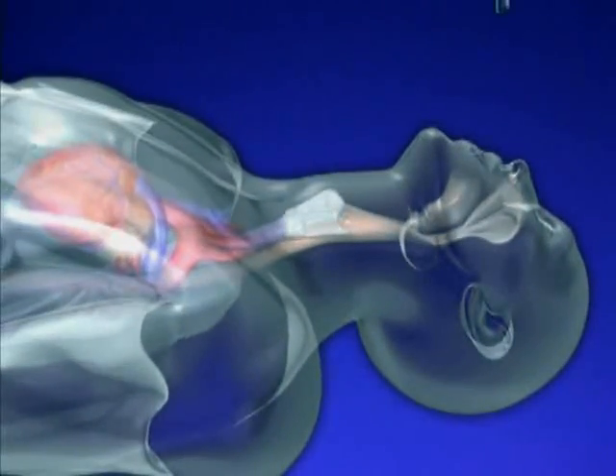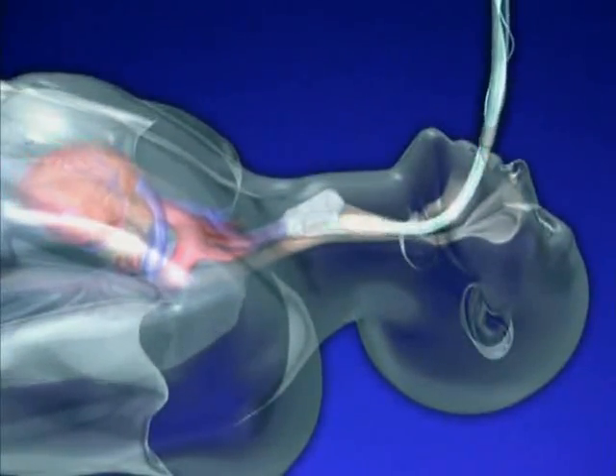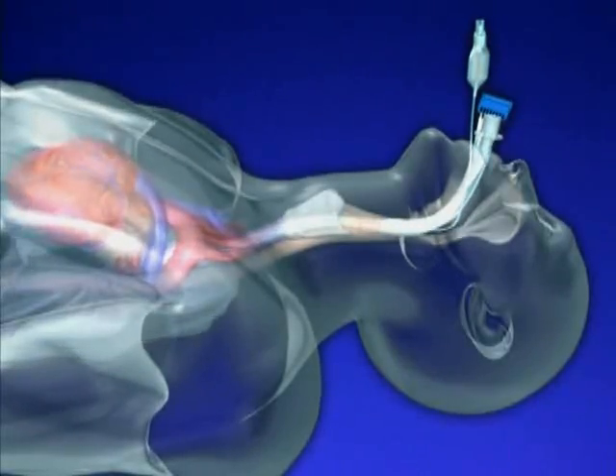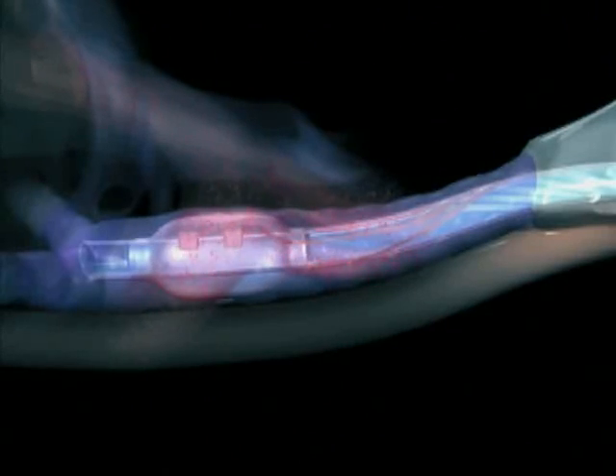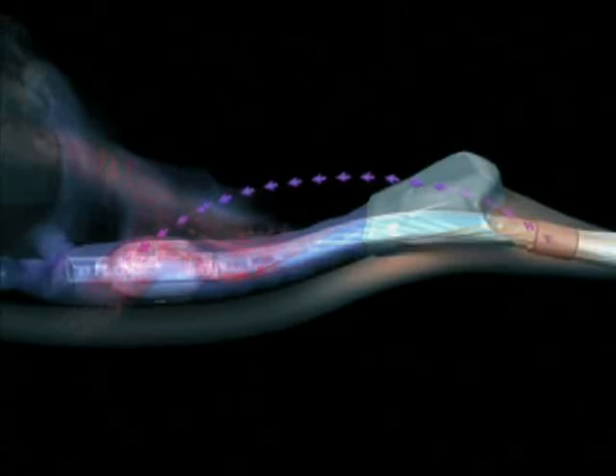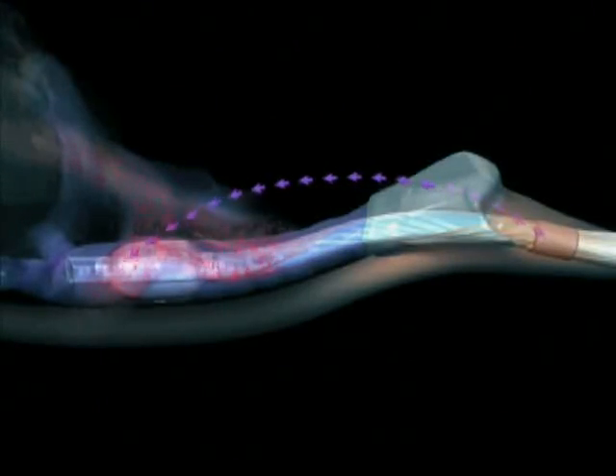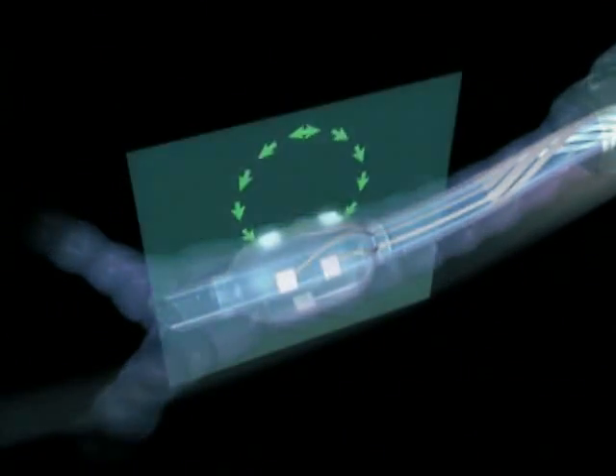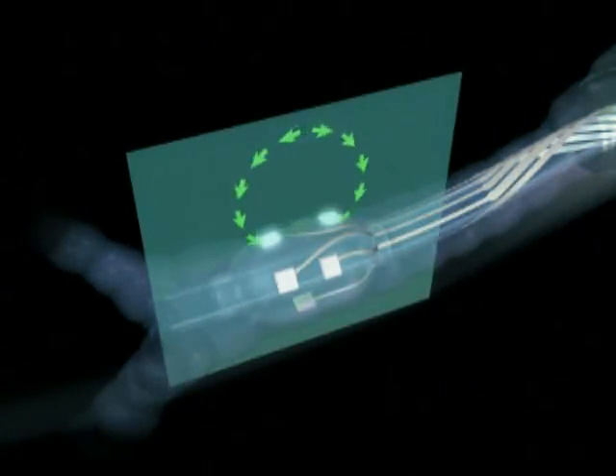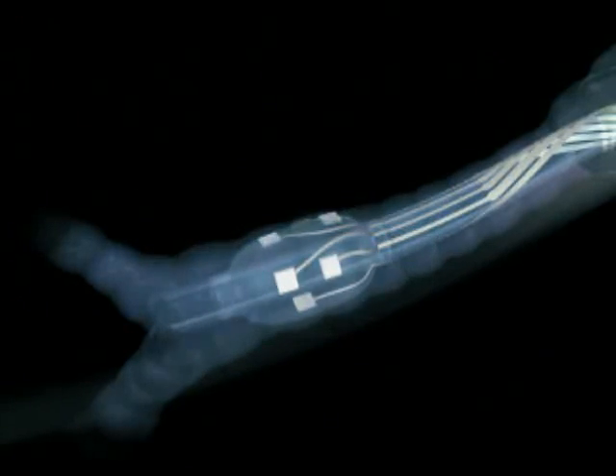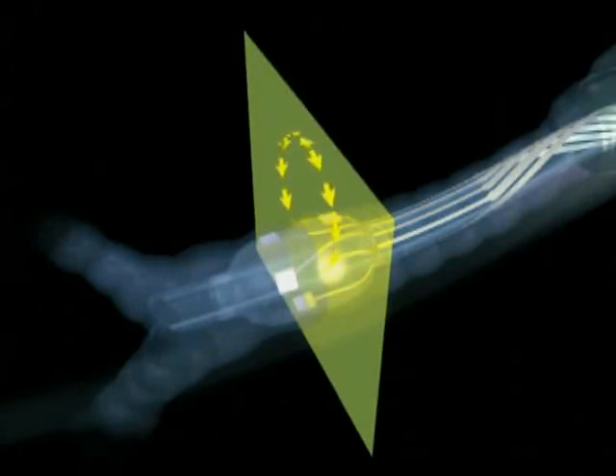First, the endotracheal tube is inserted using standard techniques. This places the cuff in close proximity to the ascending aorta. A low-voltage, low-frequency field current of 2 milliamps and 100 kilohertz is generated between electrode number 7 on the shaft of the tube and the number 3 electrode on the balloon. 3 orthogonal pairs of sensing electrodes on the cuff are used to measure the change of impedance caused by aortic blood flow. The orthogonal electrode pairs compensate for positional and anatomical differences between the cuff and the aorta.